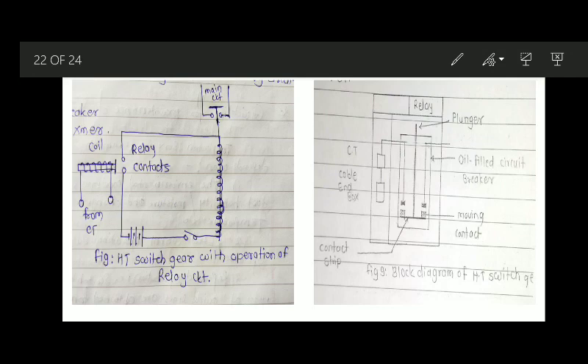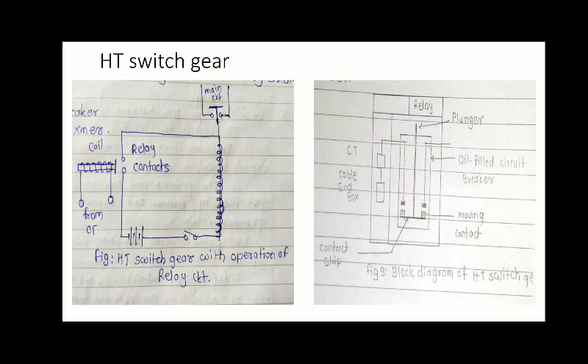After that, we want to see the operating mechanism of HT switch gear. So what is exactly the operating mechanism of HT switch gear? The HT switch gear consists of closing, tripping and interlocking mechanism of circuit breaker, usually connected to common bus bar. The isolators are provided on both sides of the circuit breaker to disconnect them or to make them dead from live part, to keep them ready for repair and maintenance without any danger. The electrical or mechanical interlocking helps the circuit breaker to open before opening the isolator, and isolators are open before opening or removal of any cover or barriers.